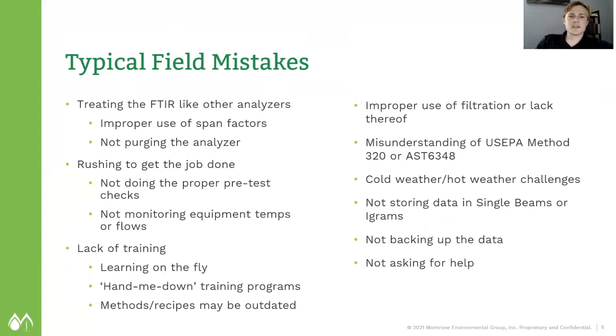Spanning the instrument to say that the gas is actually this is not always the best method. You especially should never do this to your CTS or your analytes of interest. There are times where it's okay, but as soon as your span factors get a little higher than 5%, you want to look at your instrument, you want to look at your calibrations. There's something else going on behind the scenes. Just spanning it to tell it what it should be is not the correct way to collect good FTIR data.